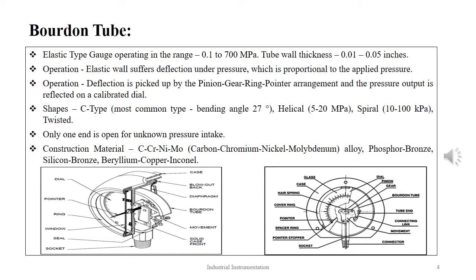There are other shapes of Bourdon tube as well, like the twisted, the helical or the spiral. The bent angle of the C-type Bourdon tube is 27 degrees. The general construction materials of the elastic medium of the Bourdon tube are carbon, chromium, nickel, molybdenum alloy, silicon bronze, phosphor bronze, beryllium copper, inconel. The free end is attached to an adjustable link with pinion, gear and ring arrangements connected to a pointer that moves over a calibrated dial.